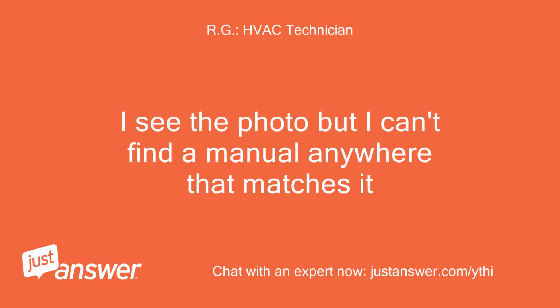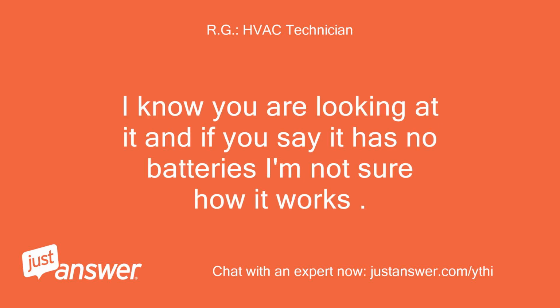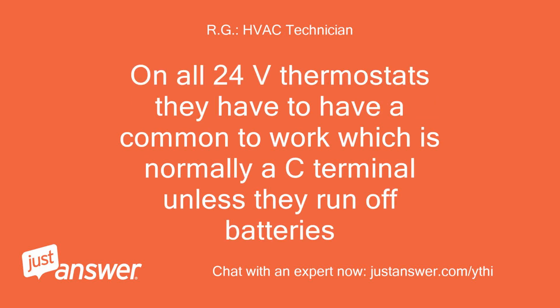I see the photo, but I can't find a manual anywhere that matches it. I know you are looking at it, and if you say it has no batteries, I'm not sure how it works. On all 24V thermostats, they have to have a common to work, which is normally a C terminal unless they run off batteries.